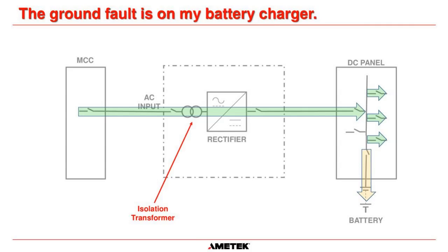because all of our DC circuits are connected on this DC bus. So the battery is connected on the DC bus, and all of these load circuits are connected on the DC bus, all in parallel. Okay, so any fault on any of the load circuits or on the battery itself will cause a ground fault to show up on the charger terminals too, because they're all in parallel.